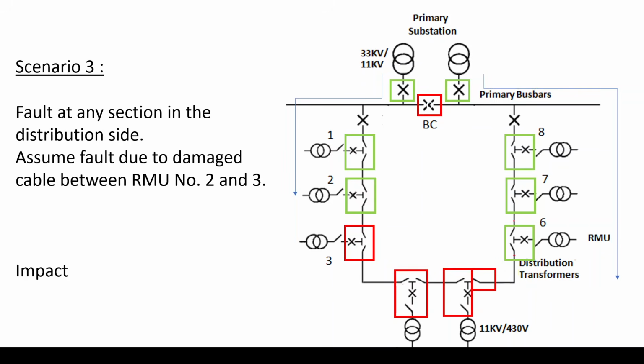So let's go to another scenario. Scenario 3: we assume a fault at any section on the distribution side. So what would happen? Let's assume a fault due to a damaged cable between RMU number 2 and 3. So here is a project or an RMU, and here is another RMU, let's say several kilometers away, and they are connected by cable. As we have mentioned earlier, the 11 kV is running, connecting both of them. So let's assume that this cable goes faulty.